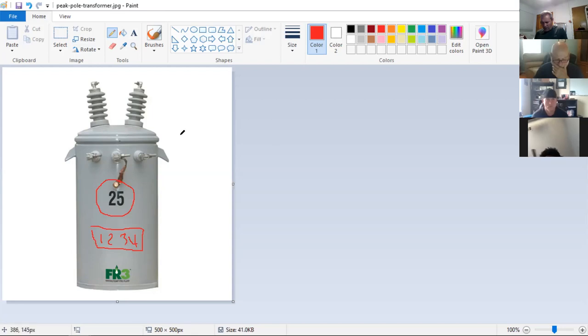Where are they getting their information from? Every single meter that's attached to that transformer. A lot of computer stuff's going on in the background. They're able to accumulate all the bill information and the kilowatt hours used. Then they take the temperature that's outside for the day. They're throwing a lot of stuff into a program that says that transformer is at 40 kVA. All right, I'm outside. It's 75 degrees, it's a calm day. If it's at 40.2 now and it's a calm day, is that enough transformer for the people that are attached to it?